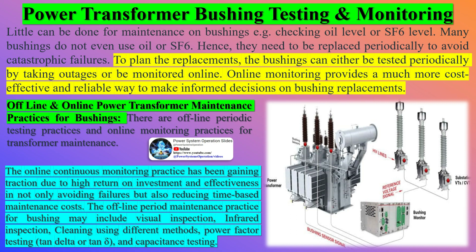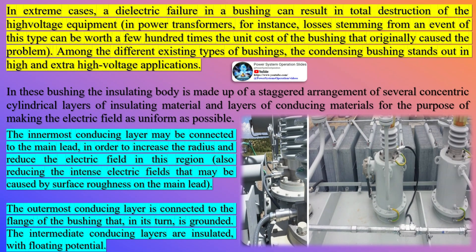How does it work? Online monitoring detects incipient faults that are not detected by offline tests. A fault's development time is typically less than the time between offline test cycles. Online systems measure the performance of the bushing at full operating voltage and temperature.